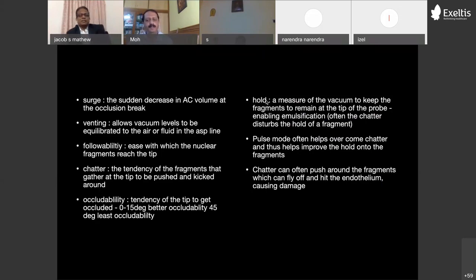Followability is something that is generated with the help of the turbulence created by the fluidics, the fluid that is coming in, so that the nuclear fragments come faster to the tip. That is called followability. So a higher flow rate means you'll have a better followability. The surgery will be a little faster, otherwise the fragments might remain there. It may not come directly onto the tip, and that is about followability.